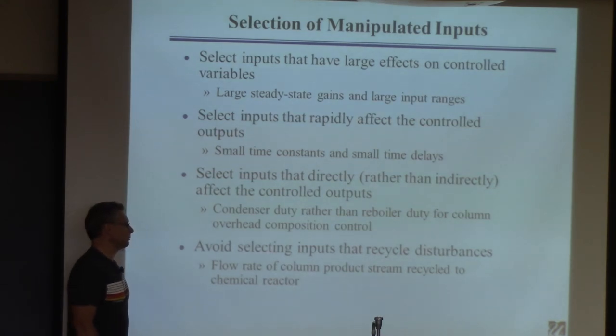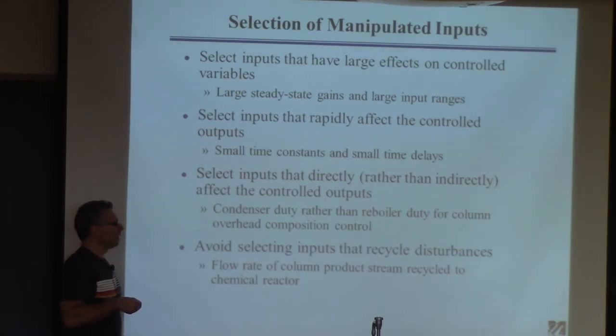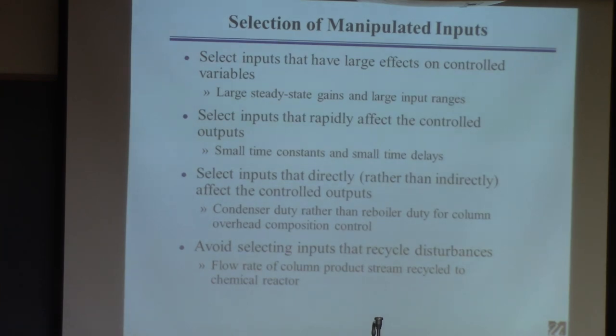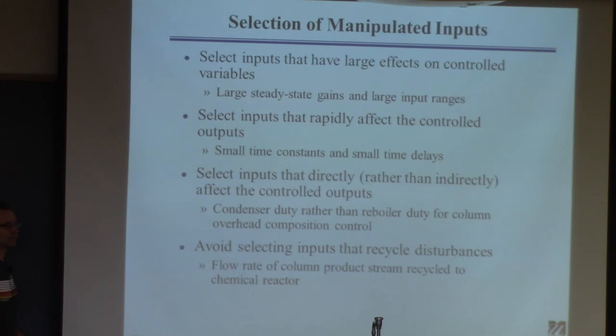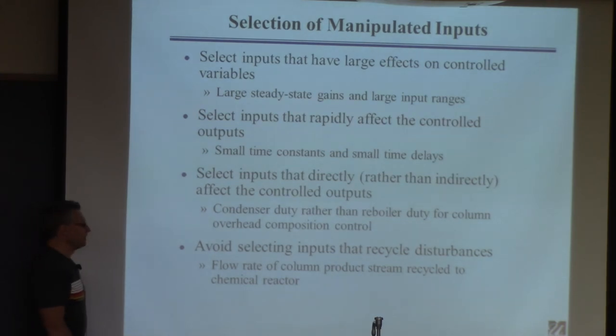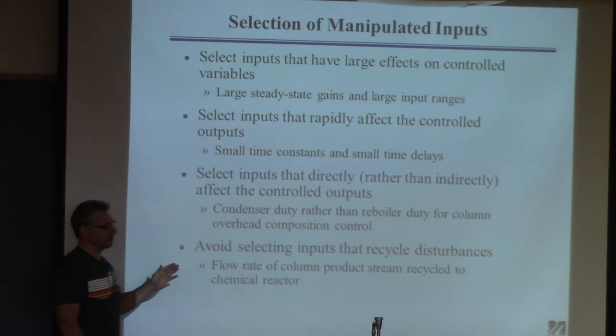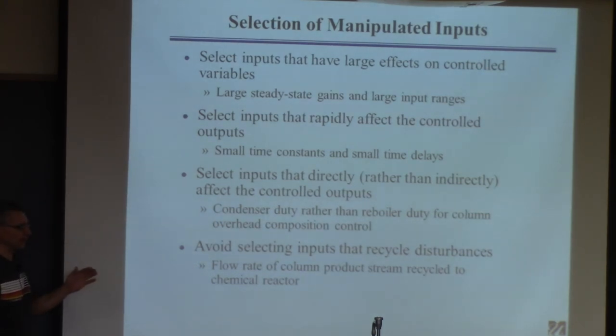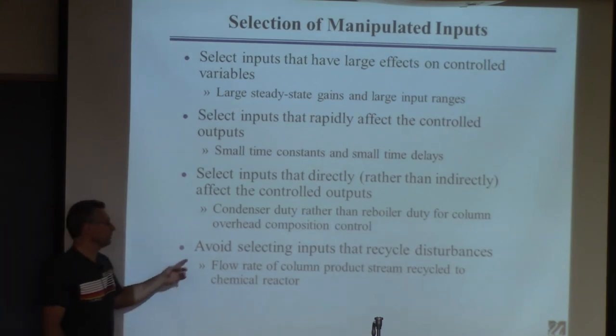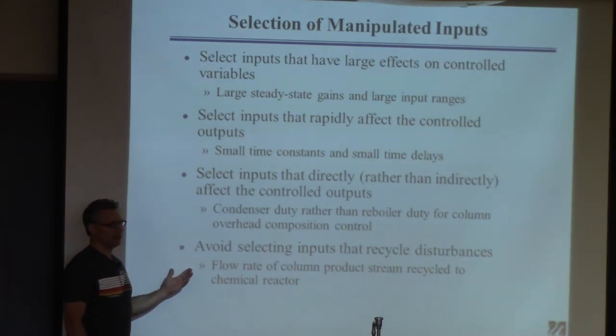Avoid selecting inputs that recycle disturbances. When you do a reaction, you usually get incomplete conversion, so you send the reactor output to a column to collect product and unreacted reactants, which are recycled back to increase yields. But if there's a disturbance coming out of the reactor, it propagates to the column, into the recycle stream, and back to the reactor — potentially amplifying because you've created feedback in the process. From a control perspective, you'd rather not do this, though from an economic perspective you often have to, so just be aware.